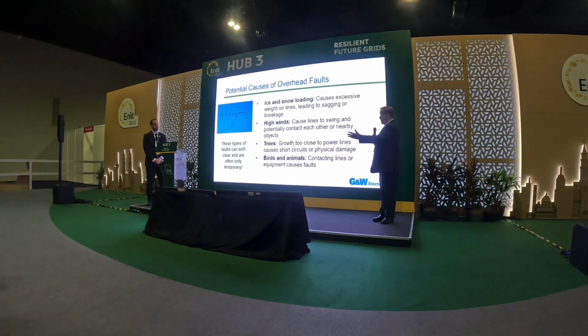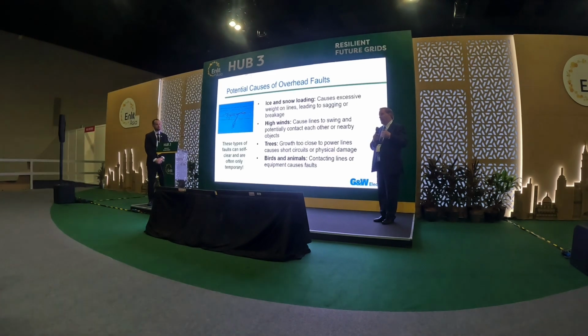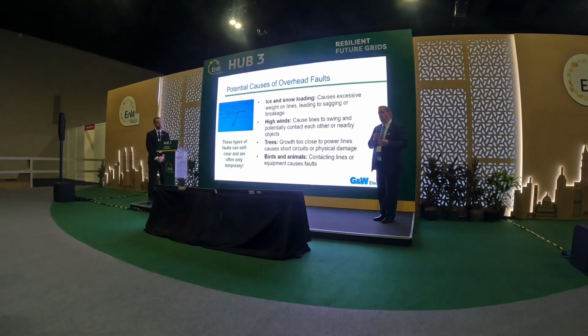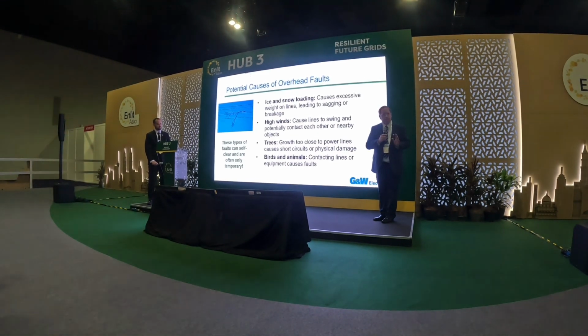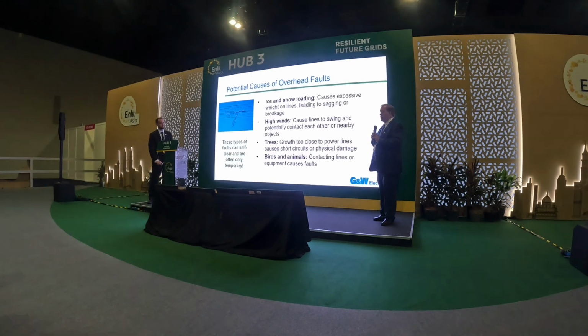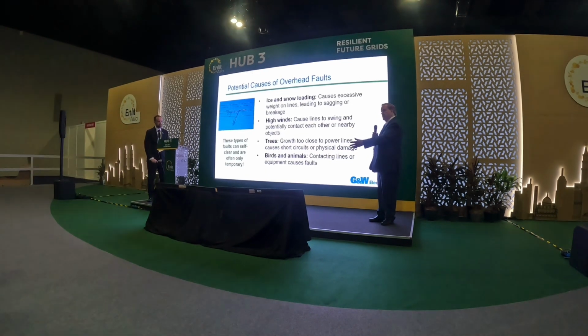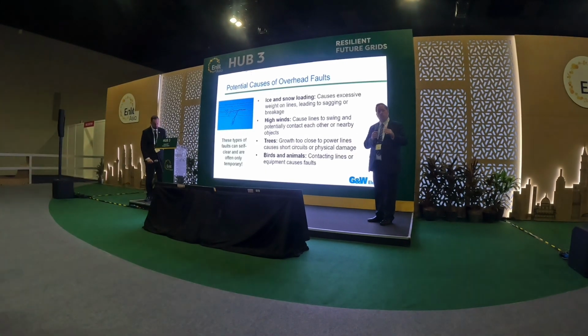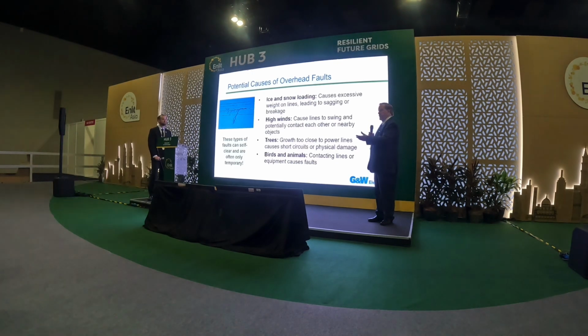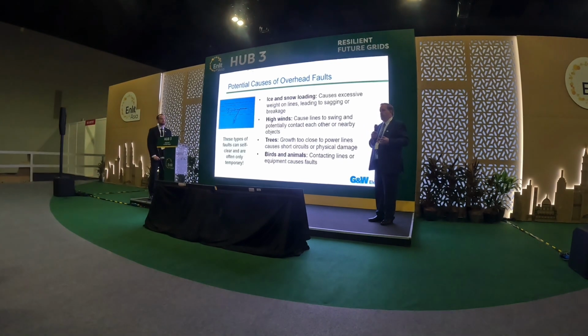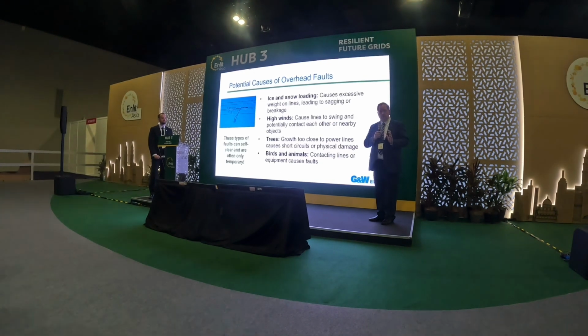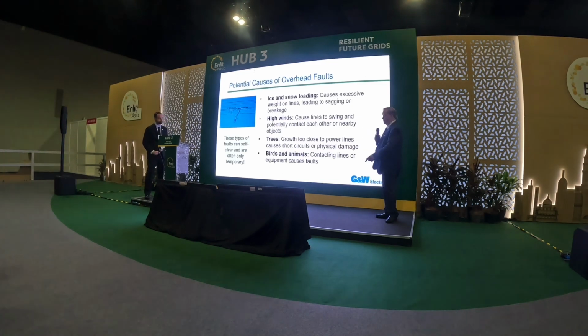And as systems transition from totally overhead, which is what historically we've had, to these underground type systems, for all the reasons Kyle mentioned, you have to start to take into consideration, what about the reclosers I have? You also may have areas where you have these type of threats to your overhead line having faults. You may have a lot of undergrounding in that area, and you might be a little bit concerned or nervous about putting reclosers in those areas. But the thing we're going to talk about in a bit is the fact you can coordinate for that.